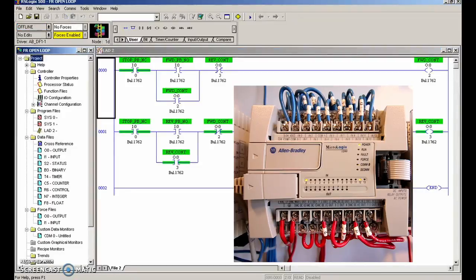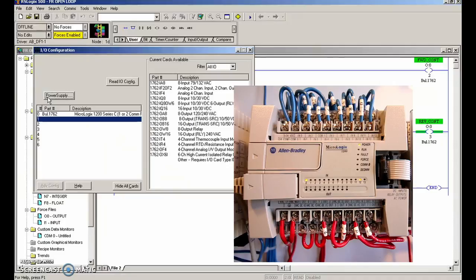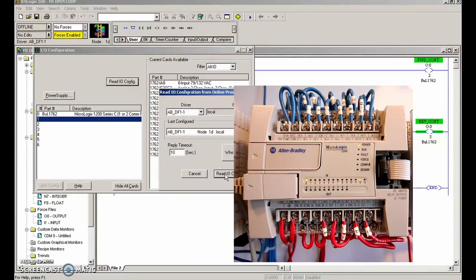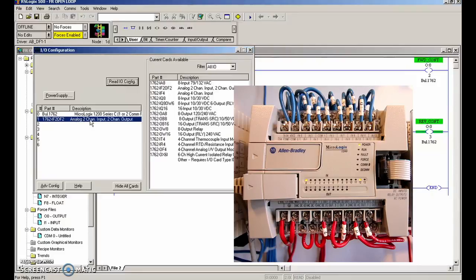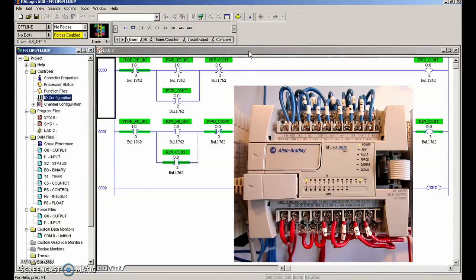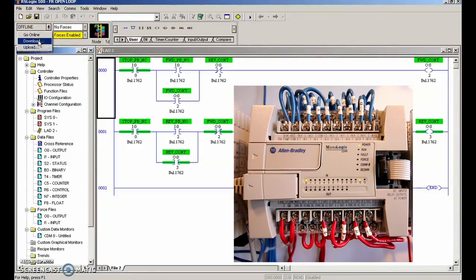We don't need to save those changes. The way to fix it is to do the IO config — we'll read the IO, and there the analog two-channel input comes in. That's why I say you might as well save your program as a base program once you've done the IO config. Every time you come back into the lab and start a new project, everything is set up and you don't get faults — because within a week you'll totally forget about this IO config.